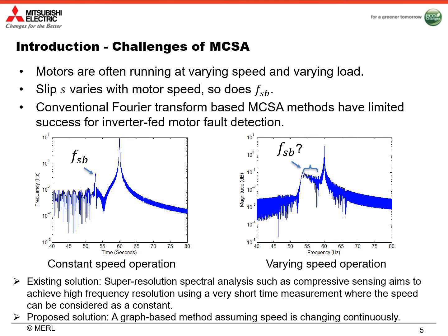However, nowadays motors are often fed by inverters and running at varying speed and varying load to save energy. In this situation, the motor slip varies with motor speed, and so does the fault frequency component. Therefore, conventional Fourier transform-based MCSA methods have very limited success for inverter-fed motor fault detection. If the motor is running at a varying speed, then the fault frequency component will spread out in a certain frequency range with relatively lower magnitude, making it more difficult to detect.